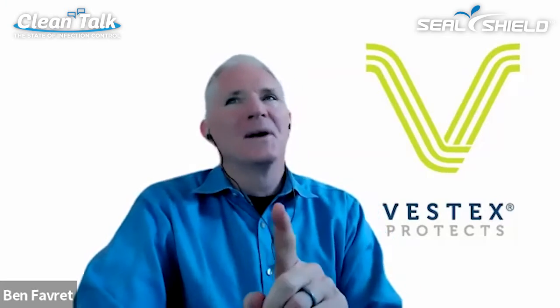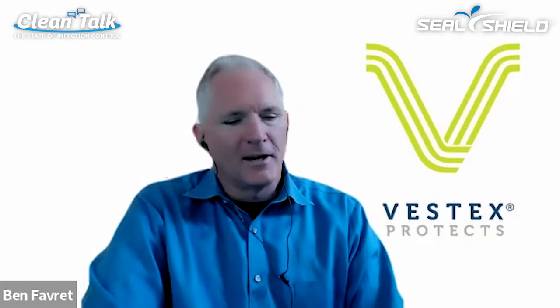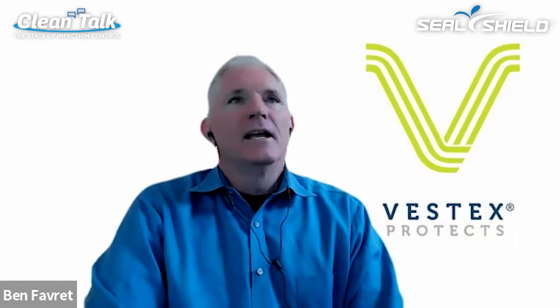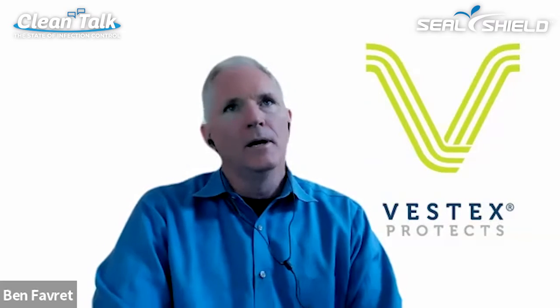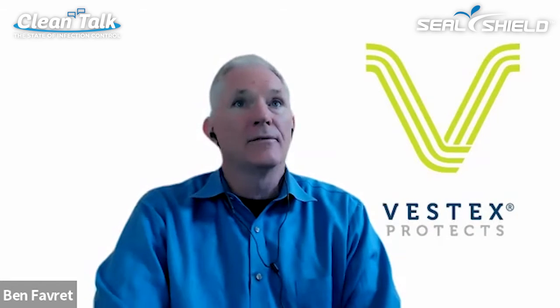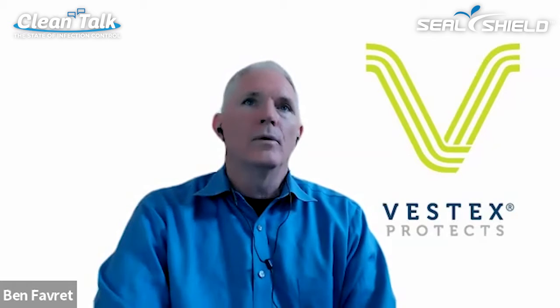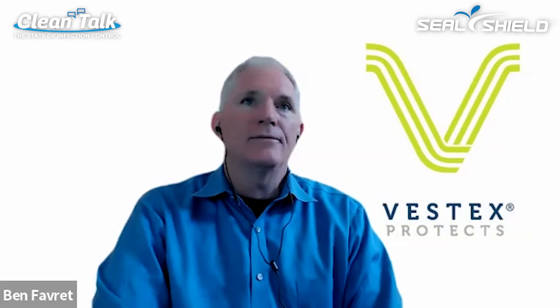It's probably the number one question we get, right? So I love telling the story too, because going through the FDA clearance process, the FDA has you validate the performance of the product, not when it's new, but after it's been through whatever you consider the life of the product. The industry standard for apparel is 25 launderings is what they consider the life of the garment.